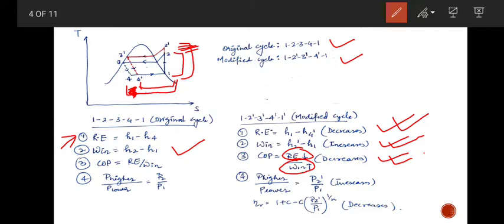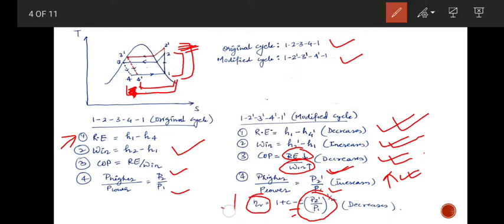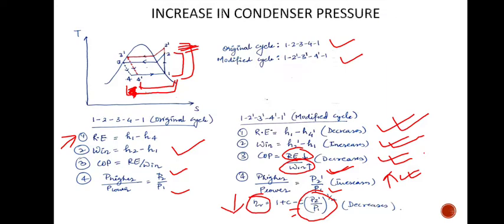For the pressure ratio, Pc2 is the modified condenser pressure which is higher, so with the numerator increasing and denominator the same, the pressure ratio increases. With the pressure ratio increasing and appearing as a negative term in the volumetric efficiency expression, the volumetric efficiency will decrease. You can compare that the effects of decreasing evaporator pressure and increasing condenser pressure are the same in terms of direction of change of all parameters.